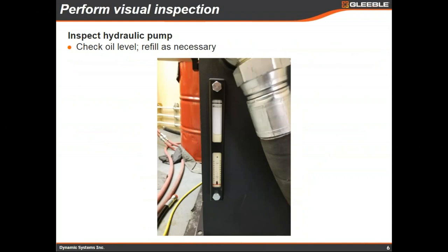Another quick check is to look at the side of the reservoir near the hose connections at the sight gauge, which indicates how much oil is in the system. If the oil level is significantly below the middle black line, you may want to add more. Something similar to what's shown in the picture is appropriate and should be good enough.